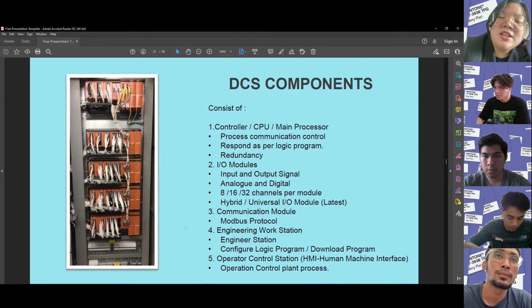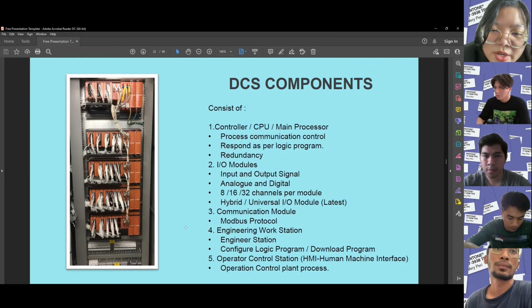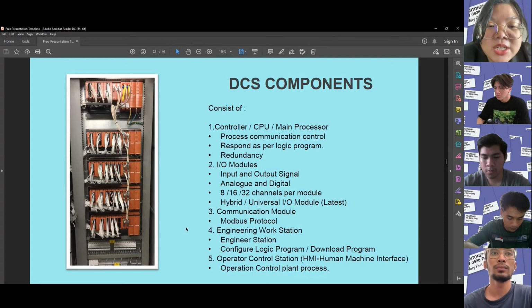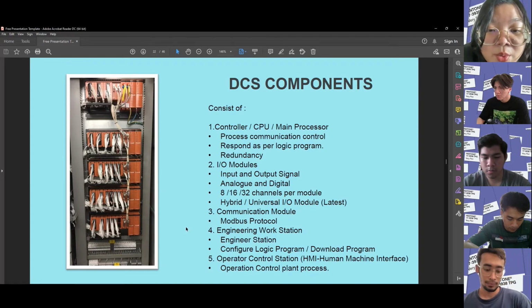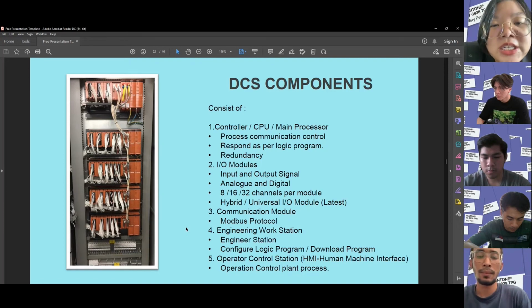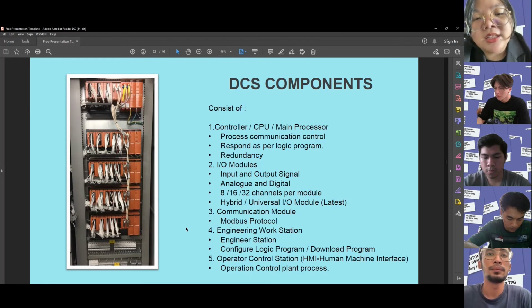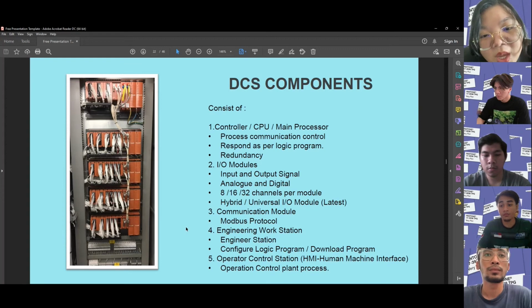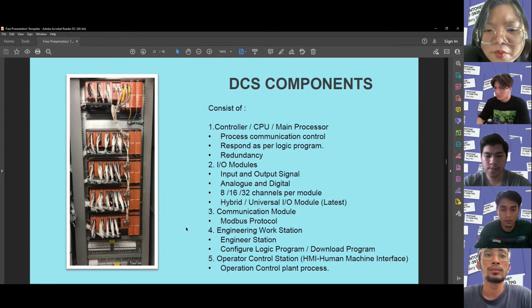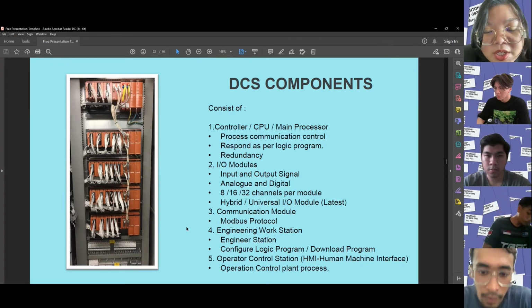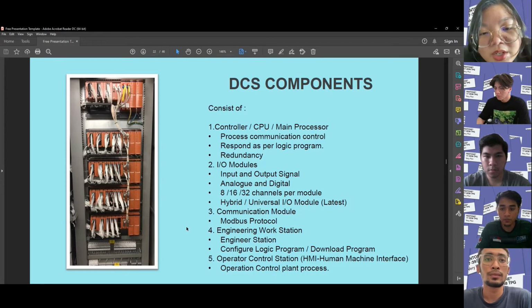Okay, DCS components. A DCS basically consists of five components. The first one is the controller, which is the CPU or main processor, and inside it has process, communications, control response as per logic program, and redundancy. The second is the I/O module, which contains input and output signals, analog and digital, and channels per module in scales of 8, 16, and 32. The last one is the hybrid universal I/O module. The third component is the communications module, which uses the Modbus protocol. The fourth is the engineering workstation, which is the engineer station to configure the logic system and download programs. The fifth, the last component, is the operator control station, which is the HMI, human machine interface, and it consists of operation control and plant process. Next.